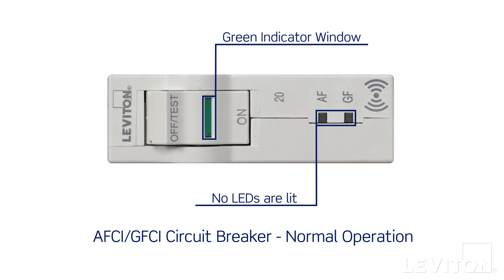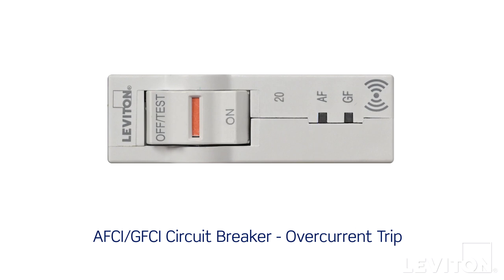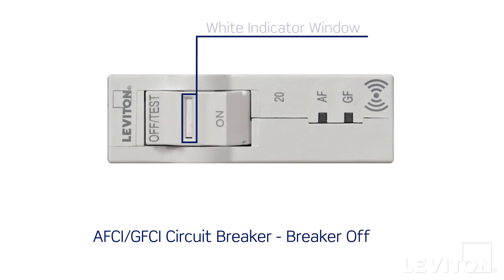If the breaker is experiencing an overcurrent trip, the indicator window turns red. As long as there's no arc or ground fault present, no LEDs will light. And if the breaker is off, the indicator window in the rocker handle will display as white and no LEDs will be lit.